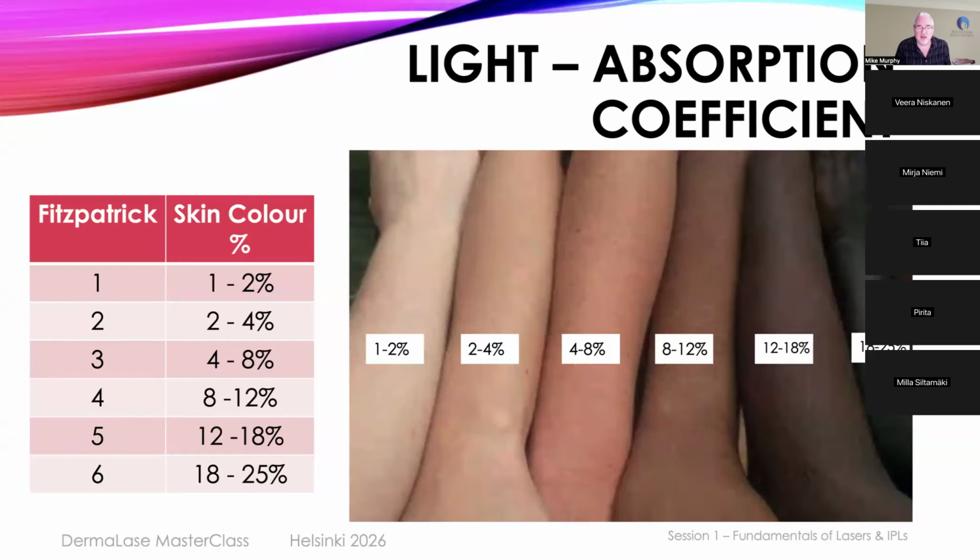It was essentially a way to determine the probability of somebody developing skin cancer if they were exposed to ultraviolet light. Now, we don't use ultraviolet light. The vast majority of skin lasers will not generate ultraviolet light. So the Fitzpatrick scale is no use to us. It's meaningless. But it has been adopted by the medical laser industry, I think probably back in the 80s. It was adopted to represent skin color, but it doesn't. That's not what Fitzpatrick meant.